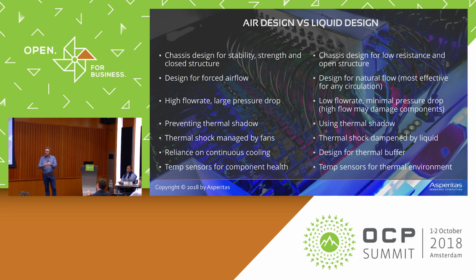The forced airflow design versus a liquid flow design is something we take to a whole different level, because we design for natural flow. That becomes very effective when designing for any immersion system. If you design for natural convection flow, you achieve a design that can adopt any type of circulation mechanism. One factor: what happens if the cooling circulation stops working? The thermal energy will keep rising to the surface and removing itself from whatever component is generating that heat.